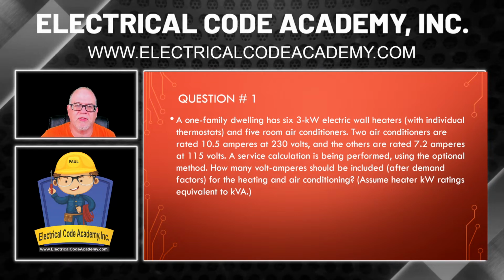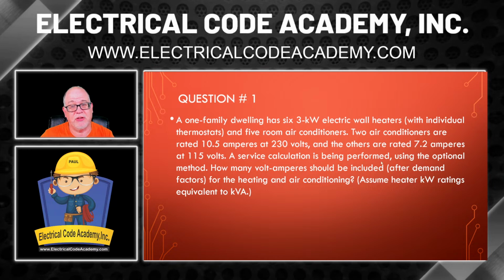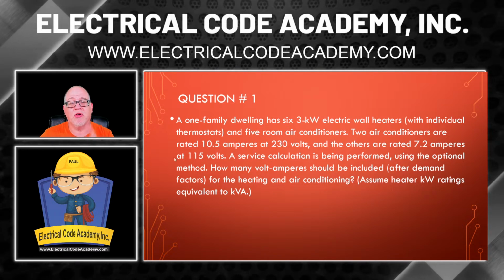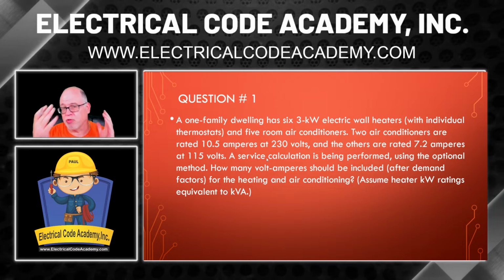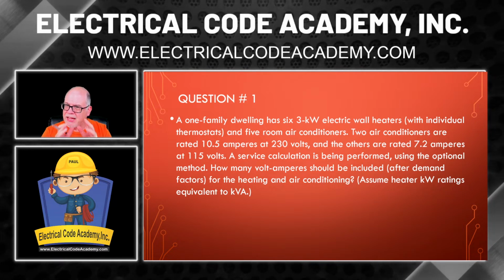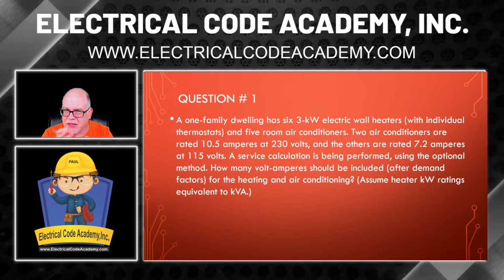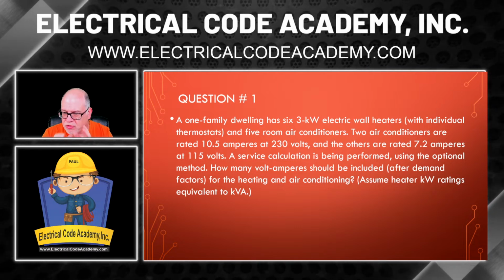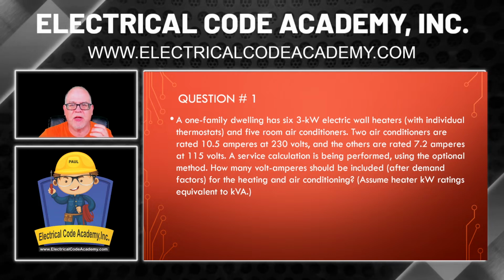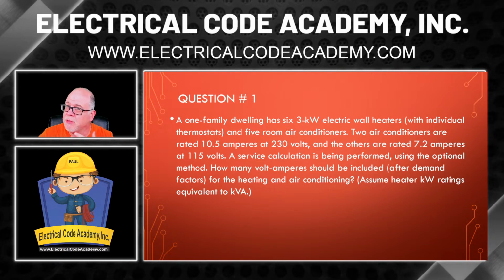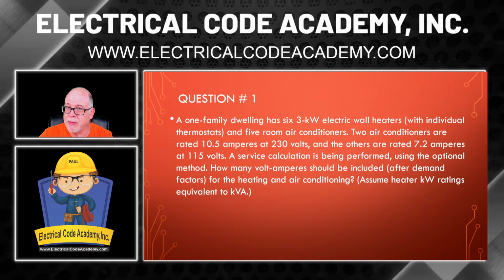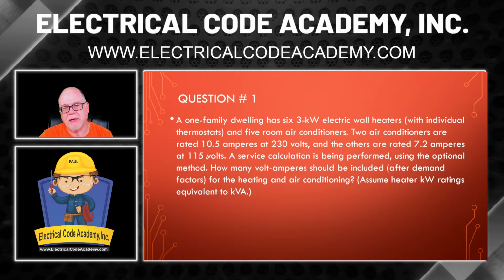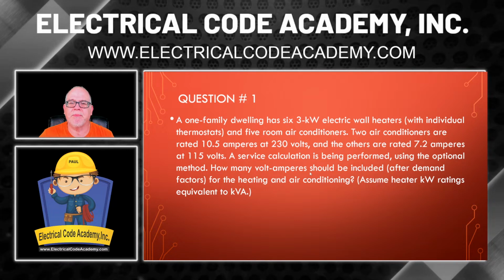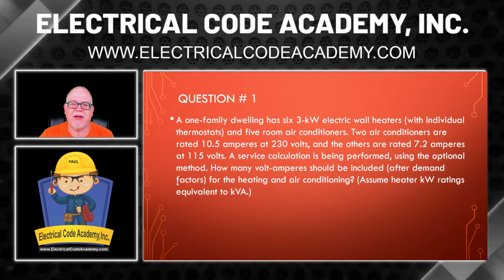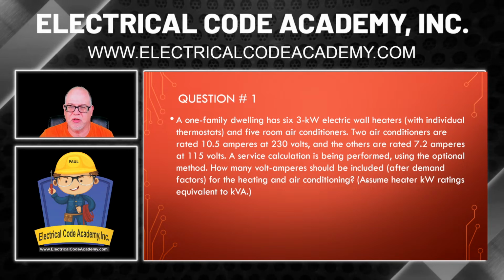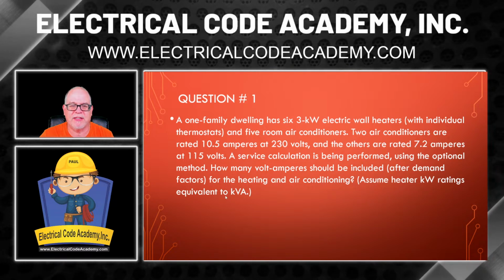All right, now it goes on to say, a service calculation is being performed using the optional method. So they'll be using the optional method to do their overall service calc. But it seems like we're only being asked to do the AC and the heat and compare the two. But it is reminding you that they're using the optional method, so that puts you in the optional area, which would be part 4 of 220, right? It says, now, how many volt-amperes should be included after demand factors for the heating and air conditioning? Assume heater kW ratings are equivalent to kVA.